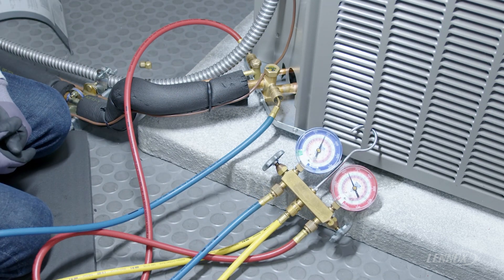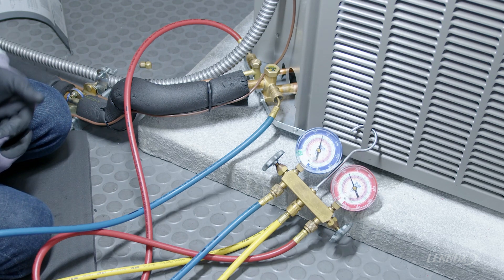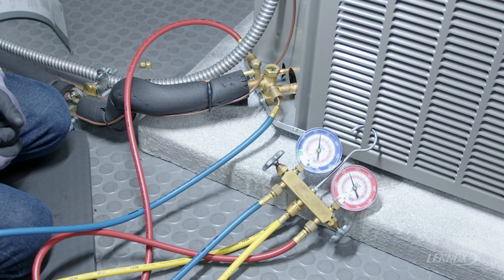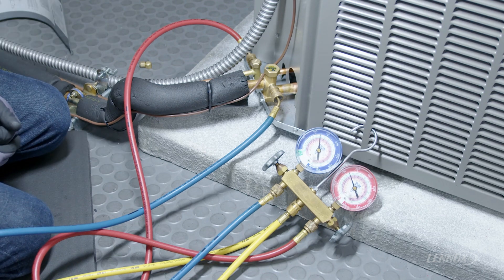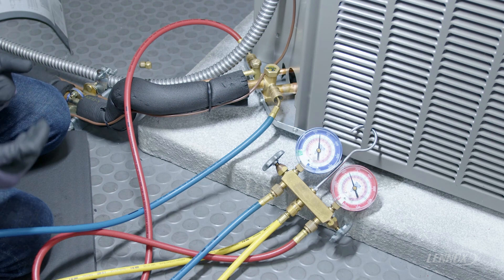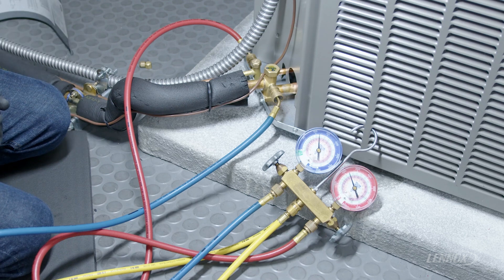An important piece to know before adequately being able to check charge is that we should let this system run for a total of around 10 minutes so that it can reach steady state operation and get a good read on pressure in relation to what the system is doing both indoors and outdoors.